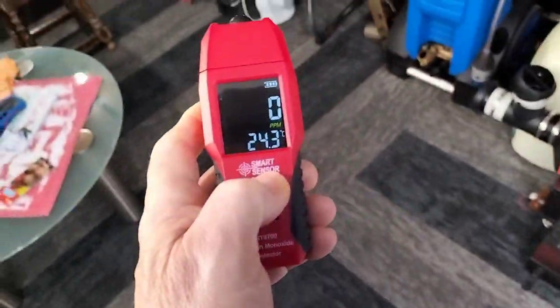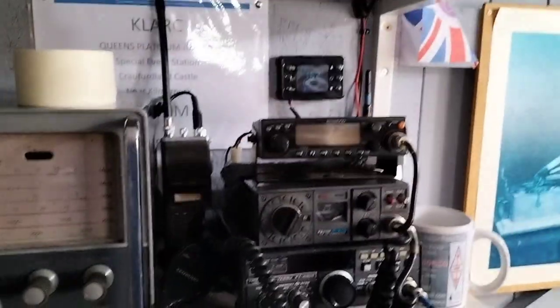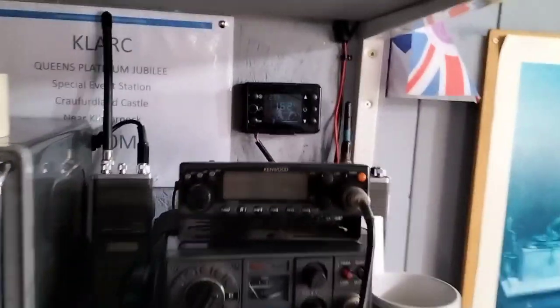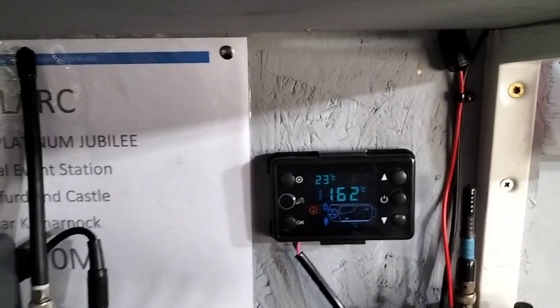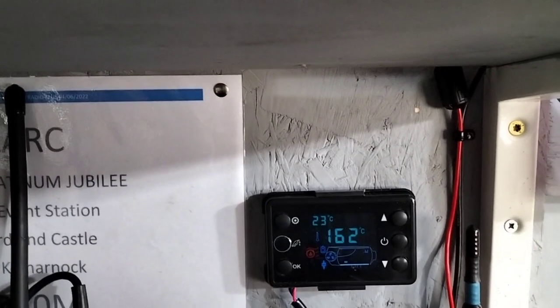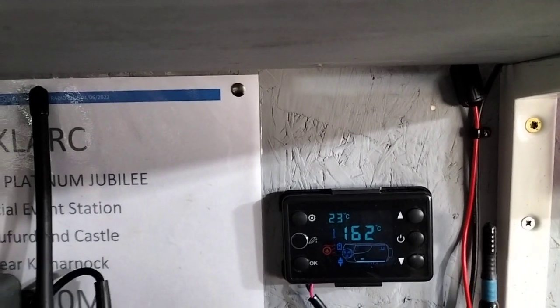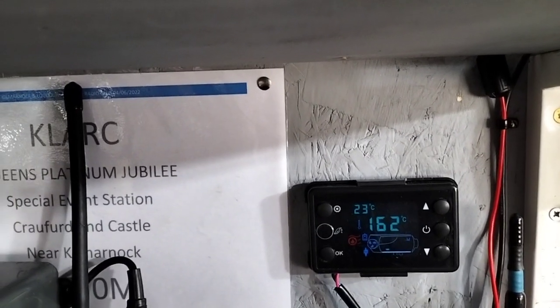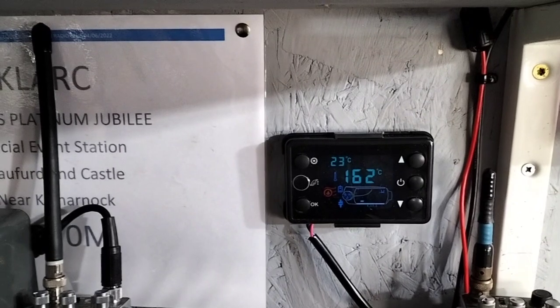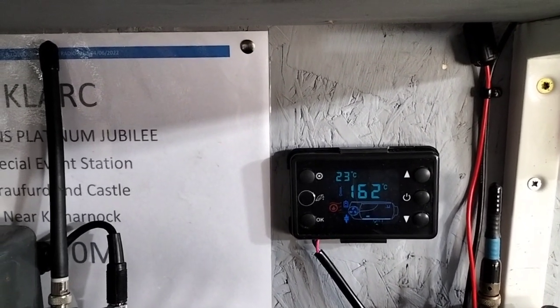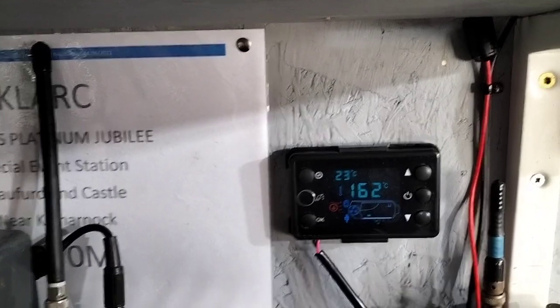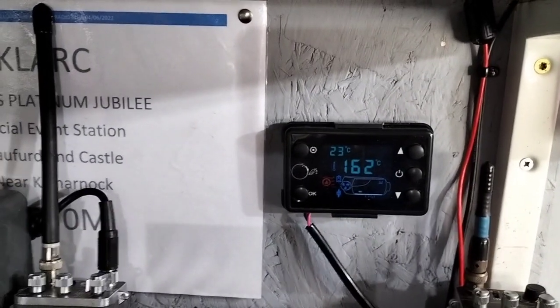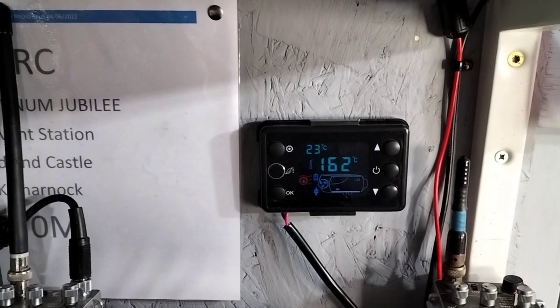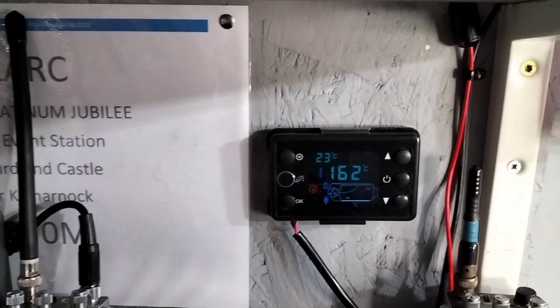So for me, the idea is when it's on through the heating up, warming up process, we have it set to Alpine mode. Once the temperature starts to get warm and the output from the unit starts to drop through the thermostatic control, once it gets to 2 or 1, we just switch it back to normal mode. 162 degrees is pretty decent on low from the heat exchanger, and the CO levels are great. So that's how I'm going to use it.